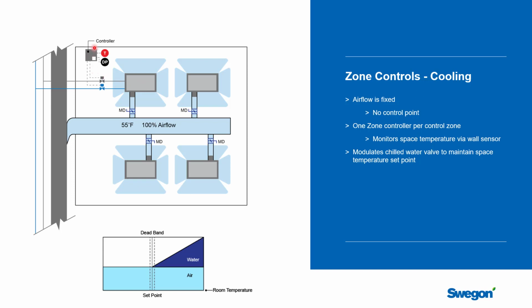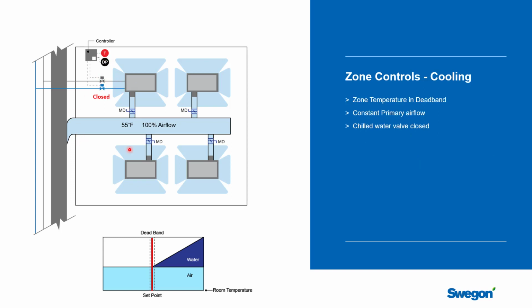And you can see that the controller, not only is it monitoring at least the temperature and the dew point and maybe indoor air quality in that space, it is also wired to the hot water valve and the chilled water valve. And so it can, if it sees a demand, either add heat or add cooling effect to the space. So let's start with cooling. So here the blue line will be our chilled water line. It's coming over here, and we're going to start. You can see with this red line that right now, from a control point of view, this space is satisfied. It's in its deadband. It doesn't need heating. It doesn't need cooling. And so both valves are closed. This temperature sensor is reading the temperature of the space and comparing it to its set point, and it's inside the deadband. So this is neutral.